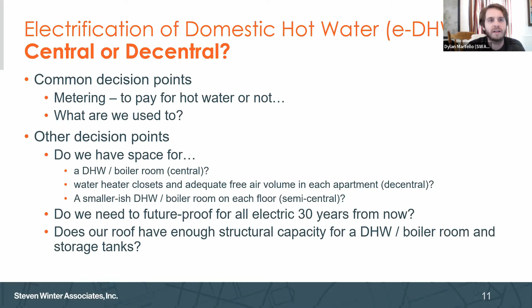Lastly, a big question for centralized versus decentralized is: do we need to future-proof for all-electric, 30 years from now or whatever that may be? What we've found is that a centralized system is typically easier to future-proof than a decentralized one. If you're installing gas lines throughout the building with gas risers for each apartment stack, it's a lot harder to electrify than if you package that into one central location. So this summarizes the pros and cons at a high level, but the goal is to produce domestic hot water with a centralized system.